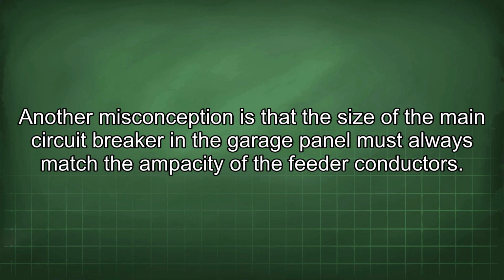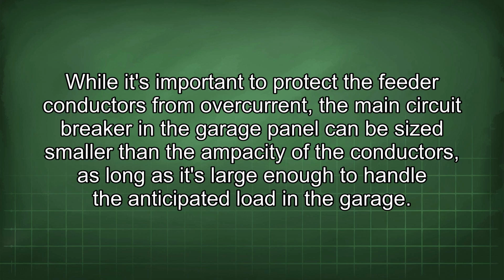Another misconception is that the size of the main circuit breaker in the garage panel must always match the ampacity of the feeder conductors. While it's important to protect the feeder conductors from overcurrent, the main circuit breaker in the garage panel can be sized smaller than the ampacity of the conductors, as long as it's large enough to handle the anticipated load in the garage.